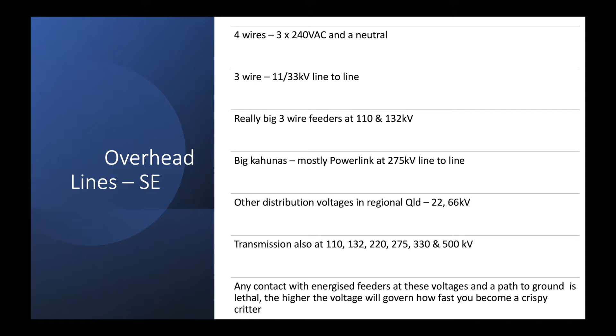In southeast Queensland, we've got a couple of different ways of getting power from the power station to your home or business. The low voltage, which should be 230 volts AC, a new standard now, or 415 line-to-line, is 4 wires: 3 phases and a neutral. That's the bottom rung of the overhead lines in your street if you've got overhead power, that's LV, what I call LV. Actually what I call LV now is 11 kV, I've changed a bit. If you see the 3 wires above it, that's now HV, or medium voltage. It could be either 11 or 33 kV, and it's 3 conductors because there's no neutral.